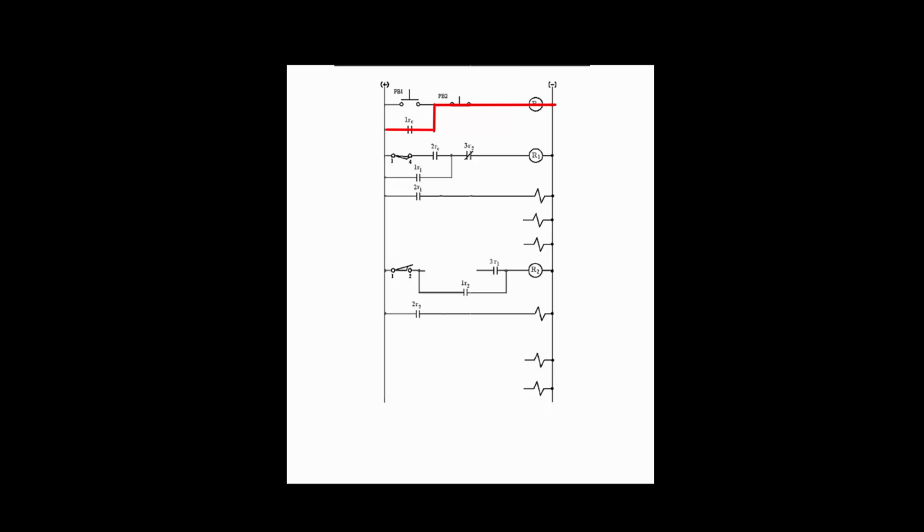Finally, how to stop the continuous cycle. It is done by pressing the normally closed push button PB2. When PB2 is pressed, it breaks the current supply to relay RC, and RC is turned off. Please note this push button PB2 is not an emergency stop button. The cycle only stops after a full cycle is completed, that is, stopping after the last action is completed.